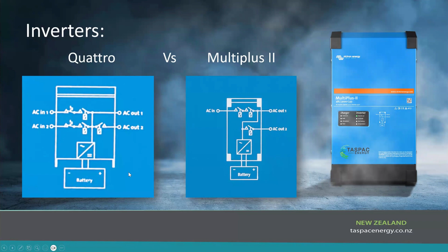Now, the Quattro inverter has two AC inputs. One can be programmed for the grid, the other can be programmed for a generator. So that's the perfect inverter if you want to have a generator backup as well as battery backup and solar for grid outages. So if you've got a customer that's really concerned about the recent disasters and storms that are coming up, or the state of the national grid or their local network, then by all means, just offer them a Quattro system and say we can integrate a generator into that. You can integrate a generator into the MultiPlus II, but it is risky because sometimes it will be rejected, and that's a discussion for our super technical training later on. But don't specify that out of the box. Always jump to the Quattro if you want to run grid and generator.